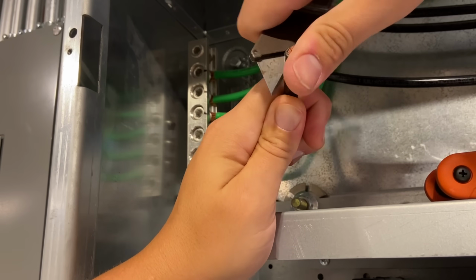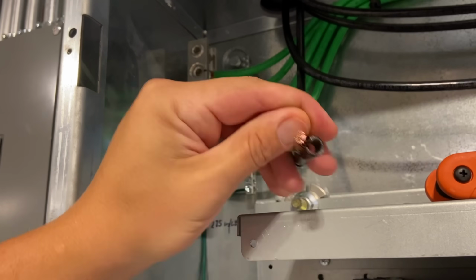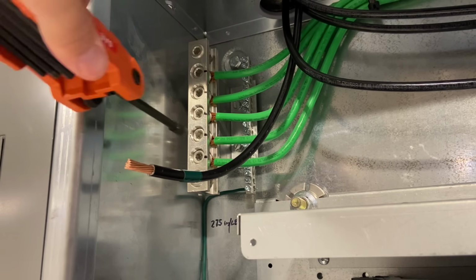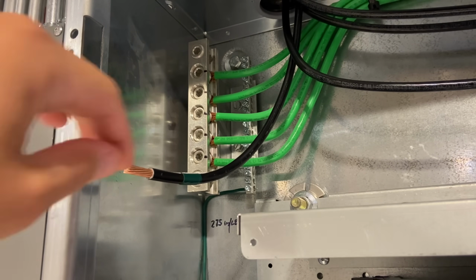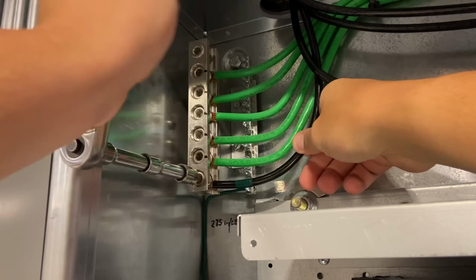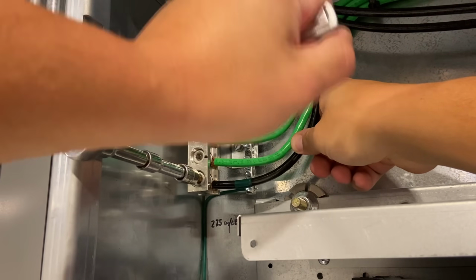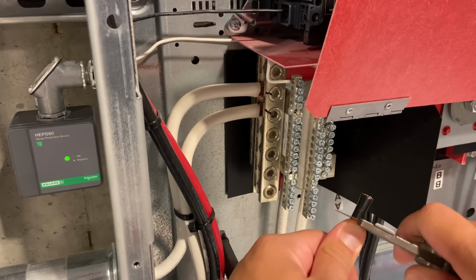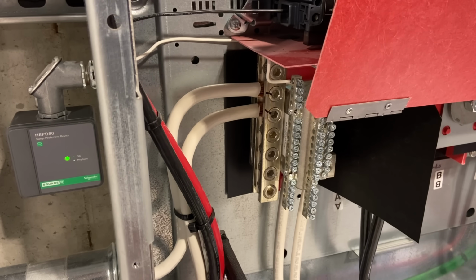Now we move on to the I-line panel, and it's pretty much the same thing, we're just playing with bigger lugs. Ground in the ground bar, as it should be. I even wrote down the torque spec back in the day when I wired this thing originally. I need to make that a sticker instead of Sharpie, but we're always improving. Neutral onto the neutral bar.